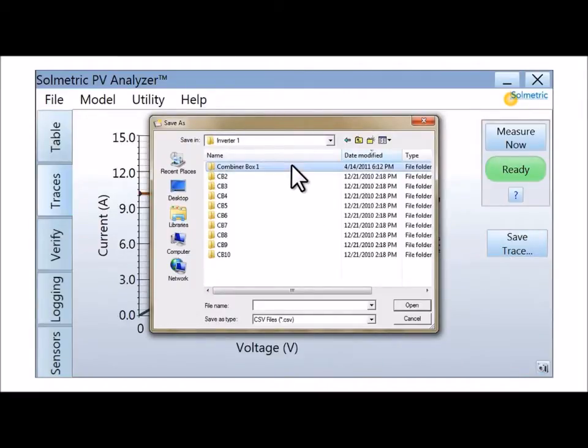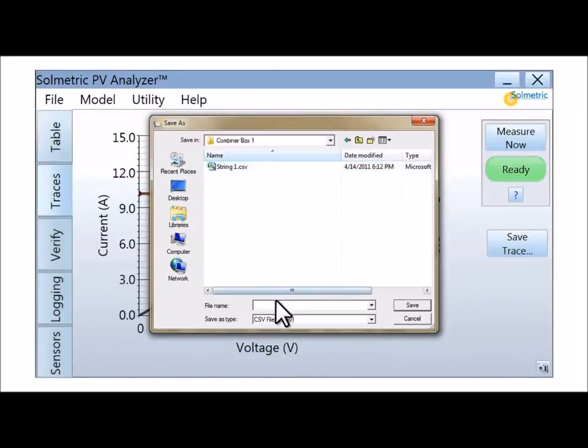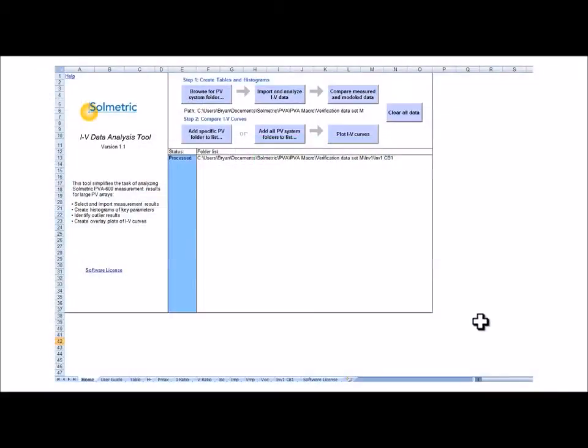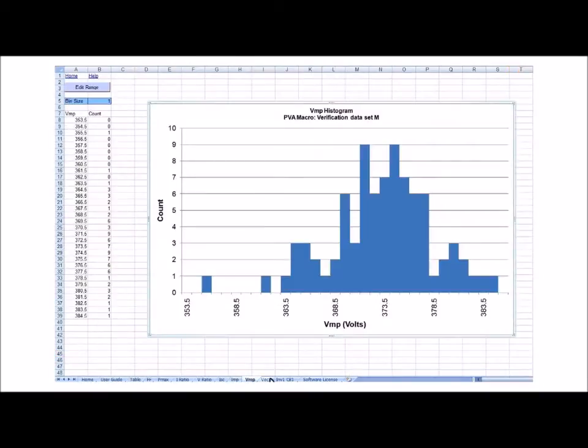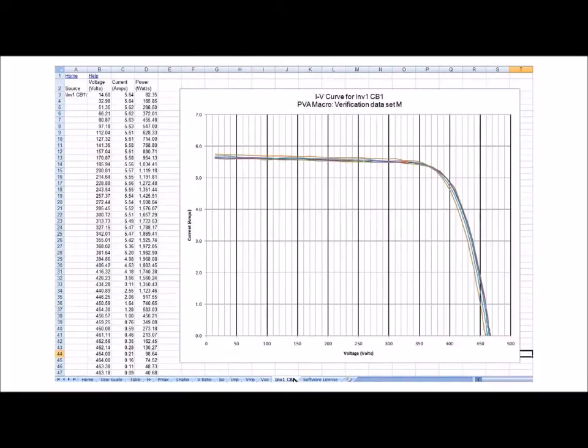Data files include a record of all the measurements made by the PV Analyzer as well as the predictions of the performance model. The IV data analysis tool provides a convenient method of analyzing PV Analyzer data. The tool imports the data from all the saved traces from a site visit and generates tables, charts, histograms, and IV plots that can be used for client reports and to identify problem strings.